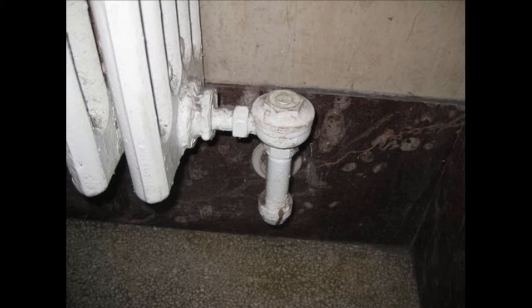At that point, we need to have about a 10 to 15 degree drop in temperature across that trap before the trap will reopen. So with a thermostatic radiator trap like this, it is possible to check to see whether the trap is working during the winter by taking the temperature here on the inlet side and here on the outlet side. You should always see at least a 10 degree difference in temperature between those two points. If you're not seeing that, there's a good chance that the trap has failed and it needs to be replaced.